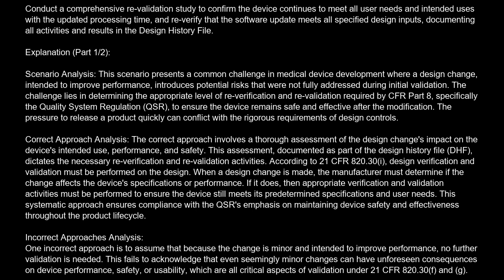Scenario analysis. This scenario presents a common challenge in medical device development where a design change, intended to improve performance, introduces potential risks that were not fully addressed during initial validation. The challenge lies in determining the appropriate level of re-verification and revalidation required by 21 CFR Part 820, specifically the Quality System Regulation, QSR, to ensure the device remains safe and effective after the modification. The pressure to release a product quickly can conflict with the rigorous requirements of design controls.